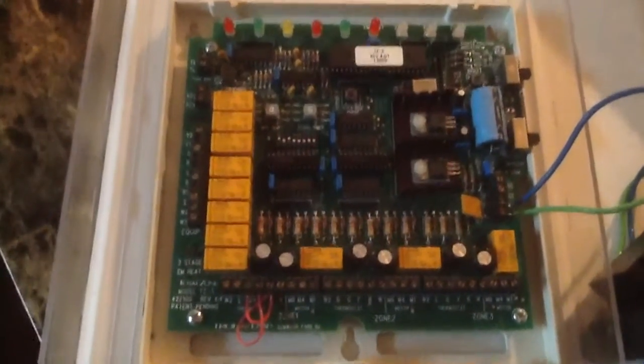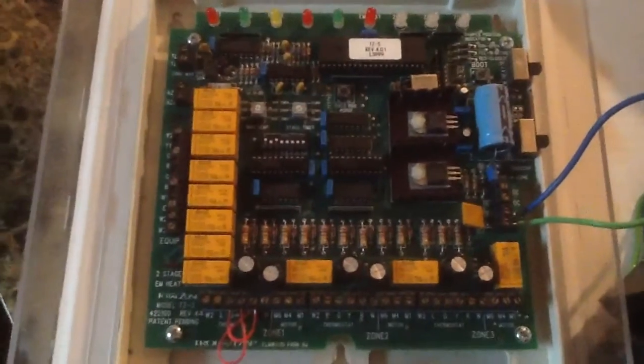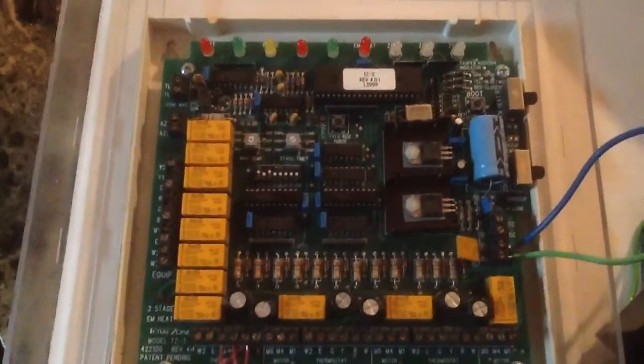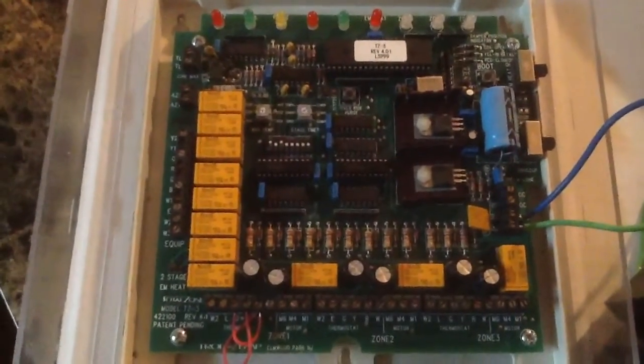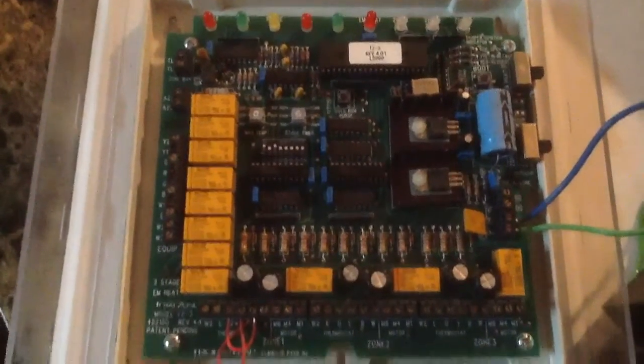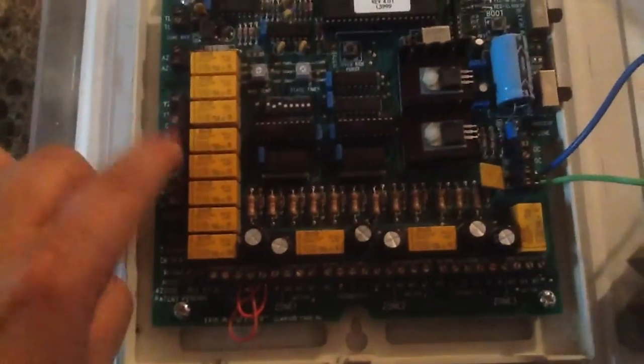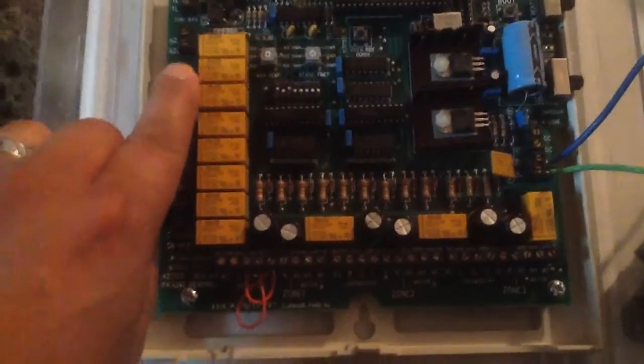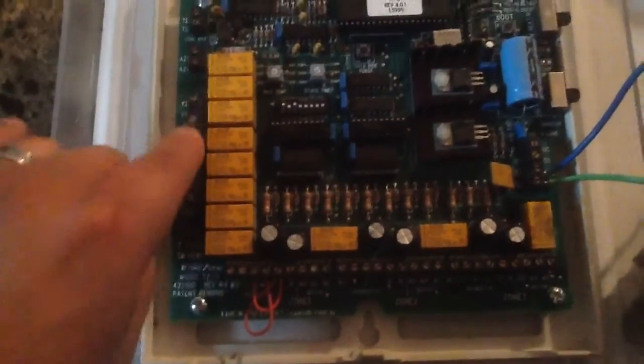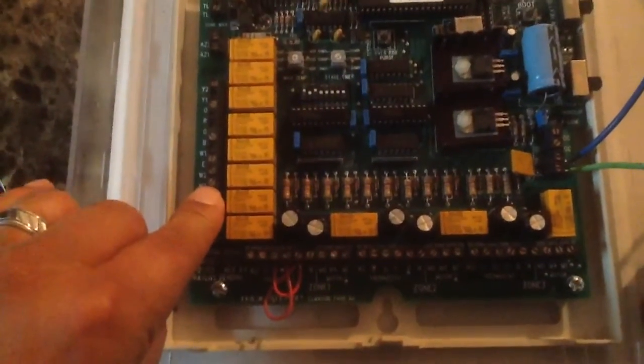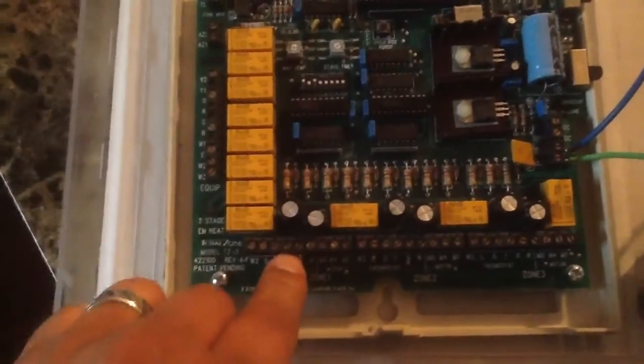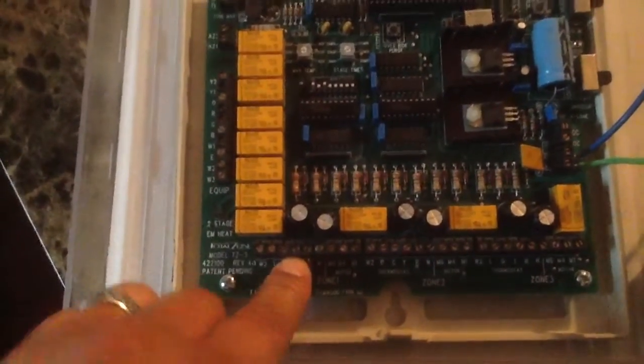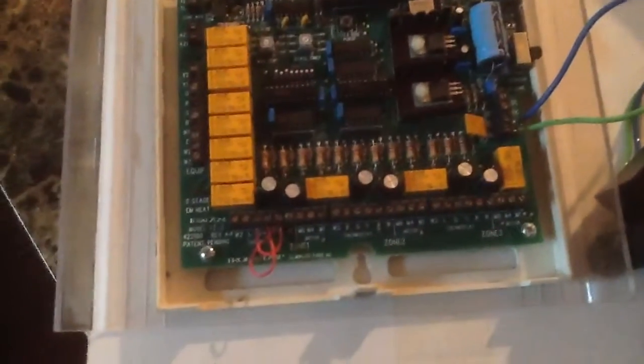But this one over here, what was wrong with it: on a call for heat, I didn't check it on cooling, but on a call for heat on any of the zone terminals here, it would not give the appropriate output. It was a straight AC with electric system for a salon, and I was getting inputs, but I wasn't getting any outputs. And that's really the only way to troubleshoot these guys.